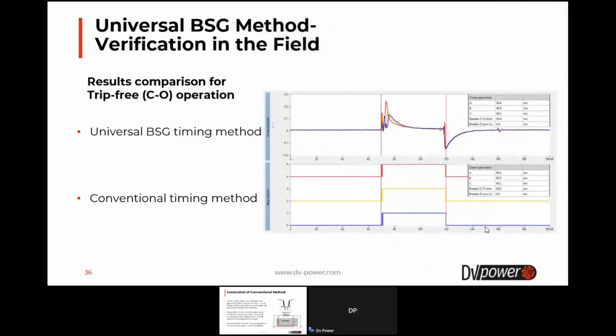And at the end, verification was also performed for the close-open or CO operation, which is shown by graphical and numerical comparison. As you can see, the close-open or dwell time is about 49 milliseconds for both methods. And this once more confirms that this universal BSG timing method works correctly.